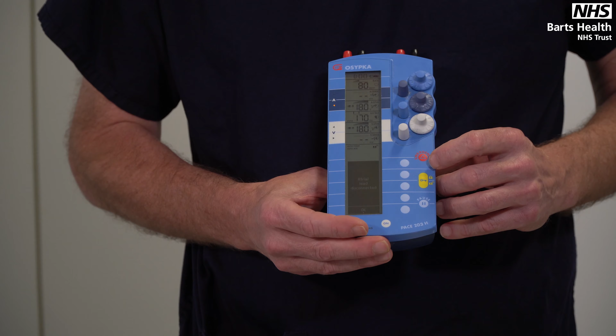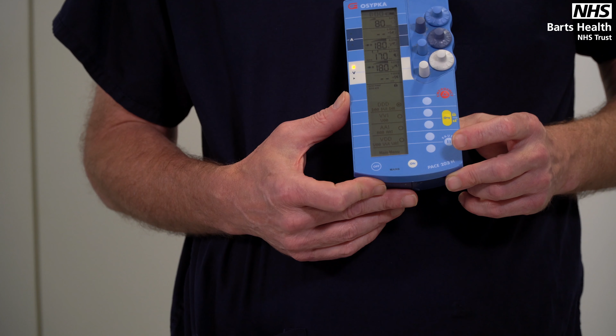At the bottom of the indicator panel are a whole series of indicators that allow you to change the mode of the pacemaker by pushing on one of the buttons on the right hand side, and they also allow access to a menu which includes further functions within the pacemaker. And then finally there is an off button at the base here which allows you to switch the pacemaker off. When you do that, it gives you the option of storing the settings that the pacemaker is set on, or clearing those completely. Sorry, one other button I should have mentioned is the pause button, which allows you to temporarily pause the pacemaker, and we normally would do that so that we can assess the underlying rhythm of the patient for a few seconds, and then by releasing it, the pacemaker will go back to its normal function.